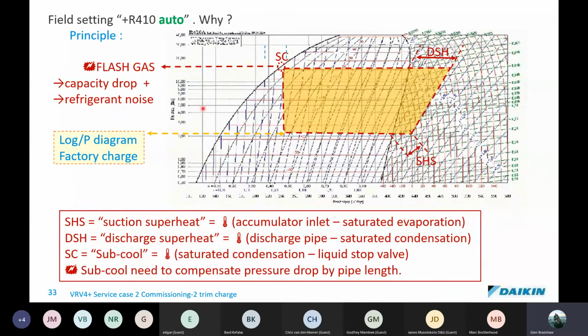Just something to consider: should you be 10% undercharged on an air conditioning system, you could be 25% short of capacity, and your system may draw 33% more power in order to try and achieve its operating or design condition. So it's very critical that we actually get the refrigerant charge correct. And so again, you do need to measure the piping accurately. That's not stepping it out, measure it with a tape measure.